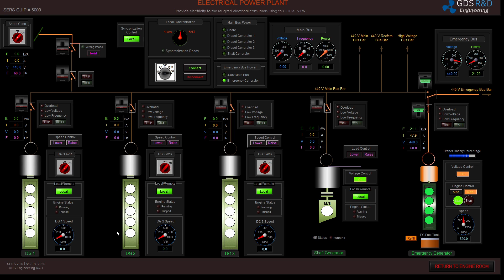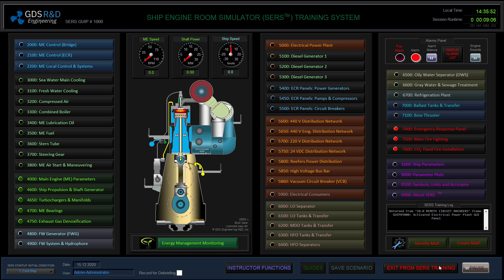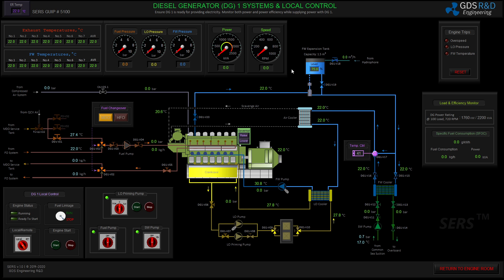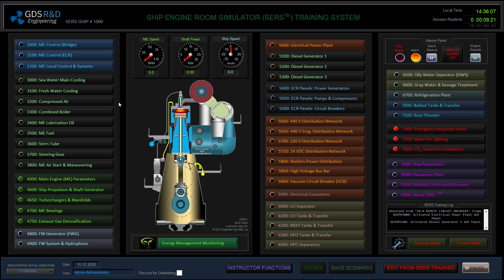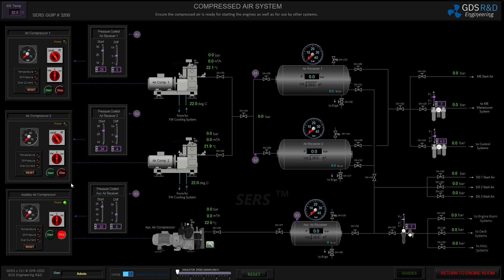I am going to start diesel generator one first, connect it to the bus bar, and then prepare the second diesel generator and perform a parallel run. To be able to start my diesel generator I will need compressed air for starting, a fuel oil system, a lubricating oil system, and a cooling system. I'm going to start by lining up the compressed air system. I can now only operate the auxiliary air compressor from the emergency bus bar.